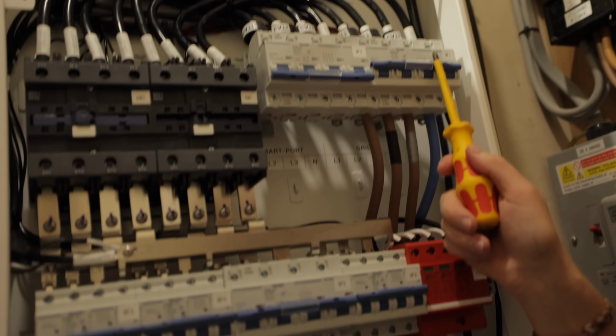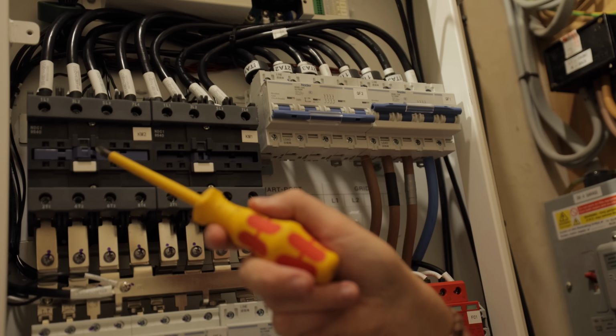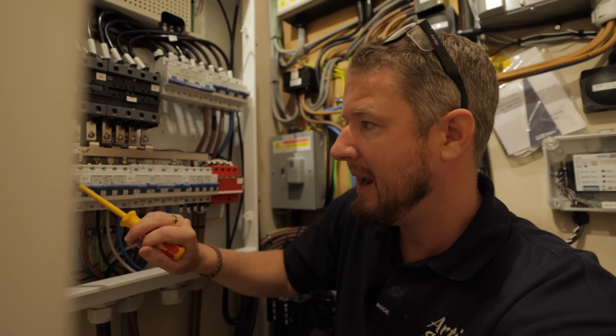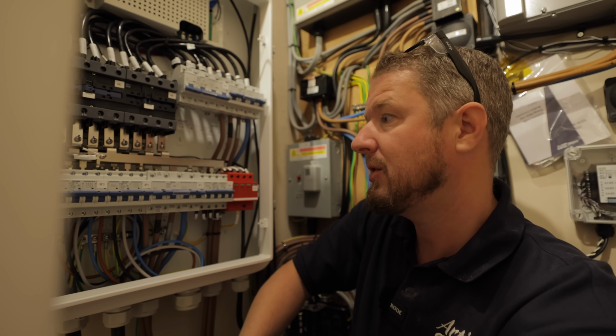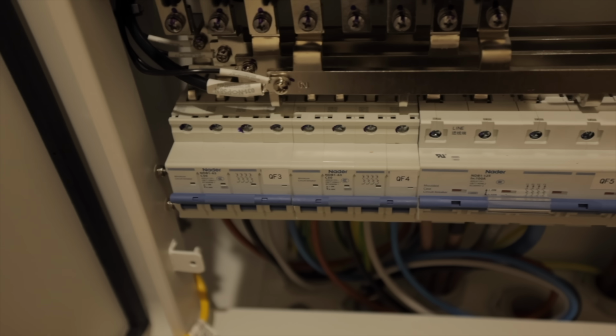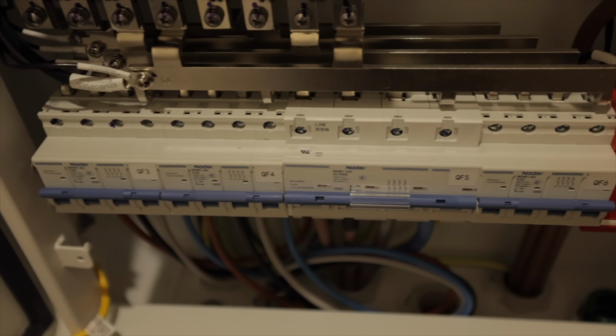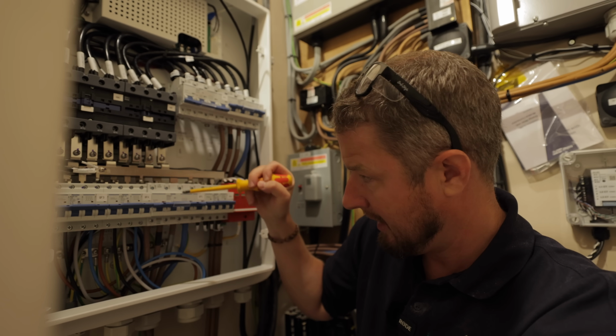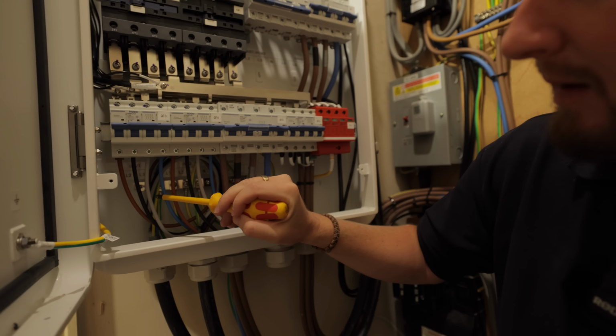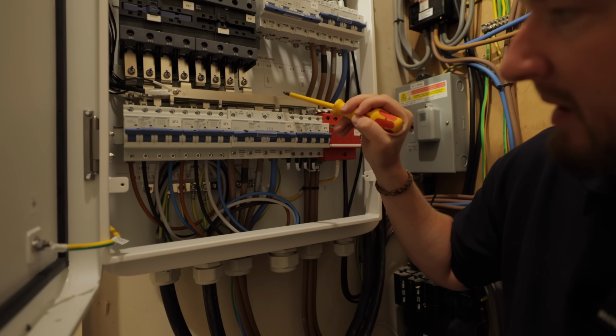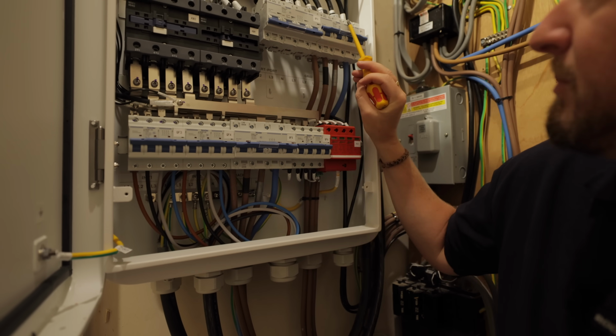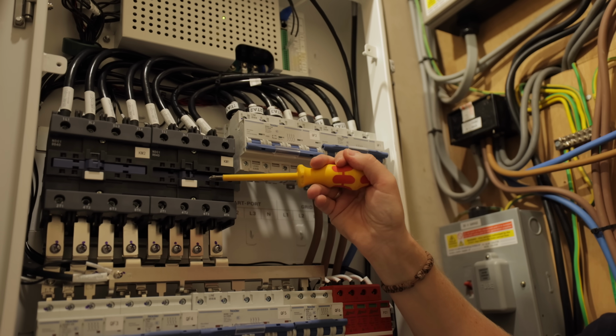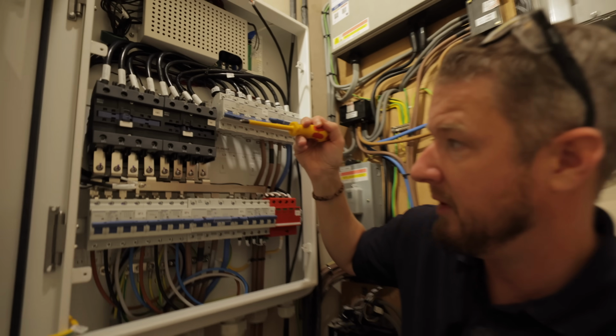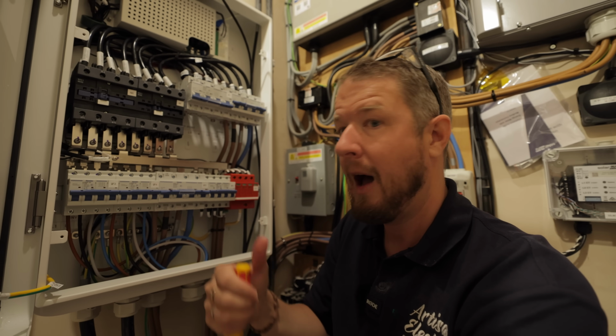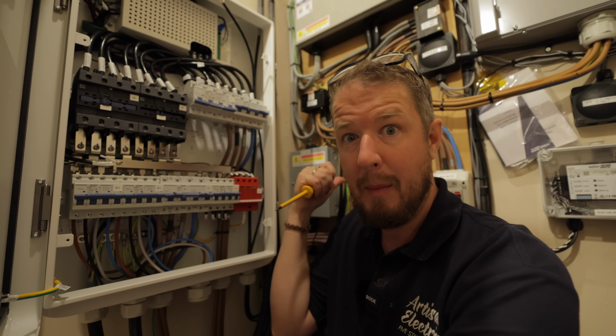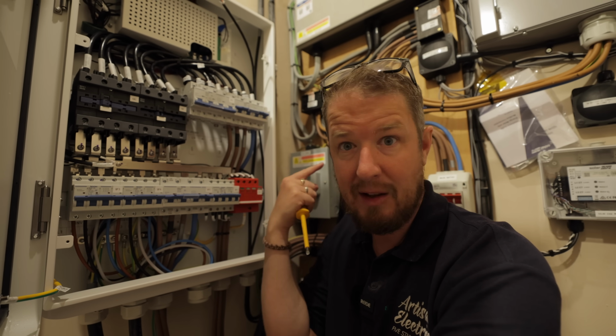And what happens is when you turn that off, this relay pops out, this one pops in, and it separates you from the grid, but it leaves the power running from the inverter. So the battery system is still feeding back into this bus bar here. This bus bar has all of the power from the inverter feeding into it, and then that feeds back down through this backup breaker, and it still feeds the house. So the power comes in from the battery and inverter, runs along this bus bar, and then out to the house. But this breaker, even though it will still be off, is isolated because this contactor here pops out. So it cuts off the supply to the grid. Because what you don't want is to have a guy working on the power line outside, he's turned the power off, but your backup system is feeding back into the grid and he can get electrocuted.